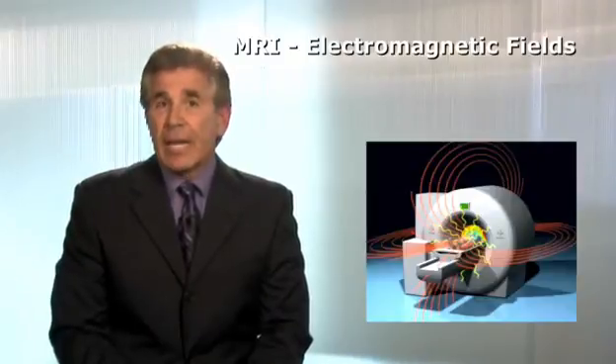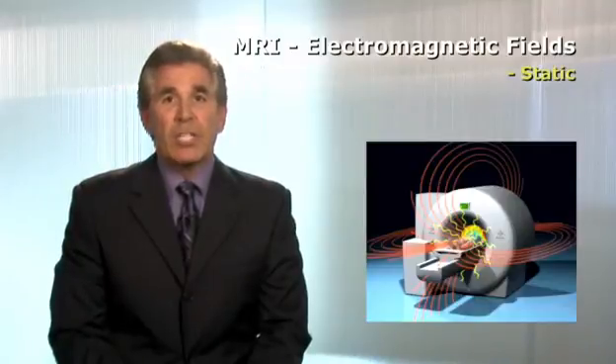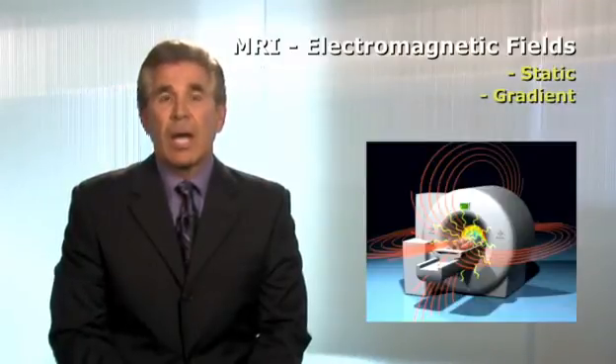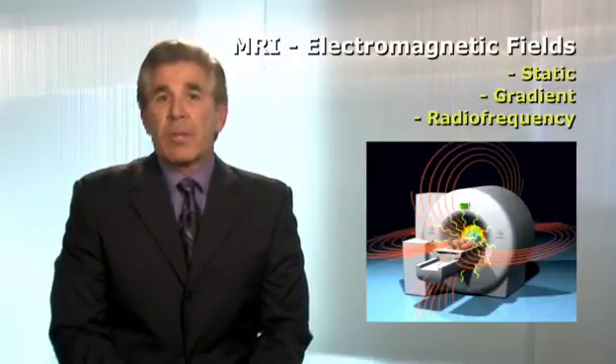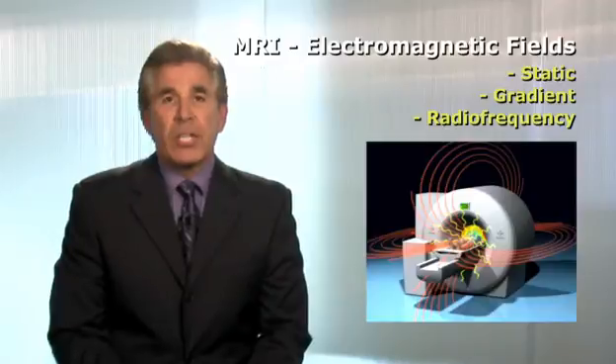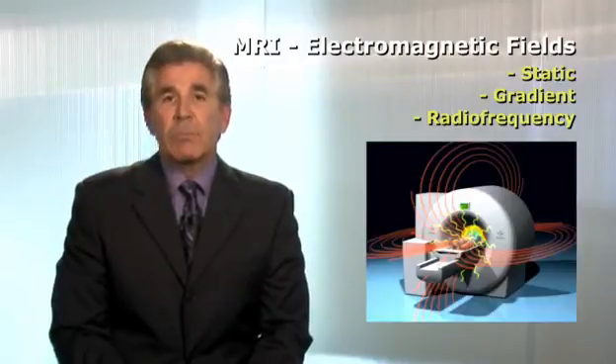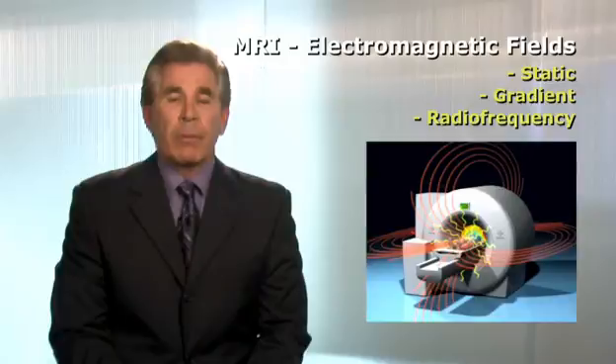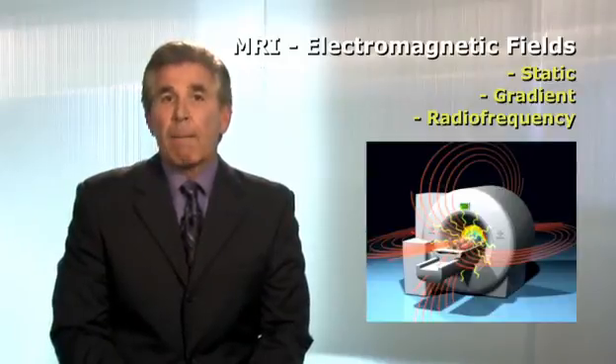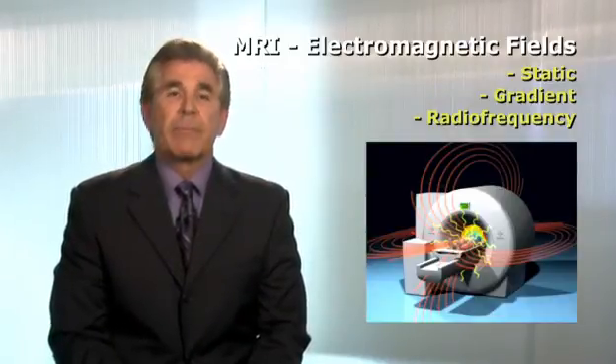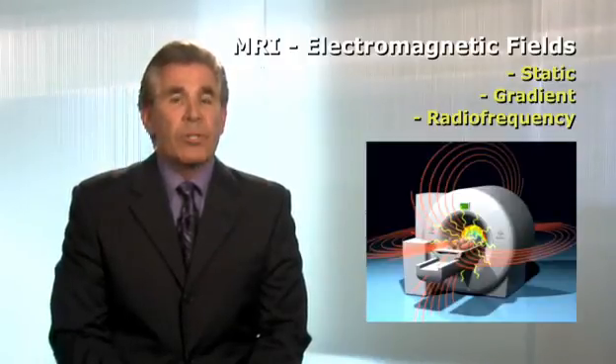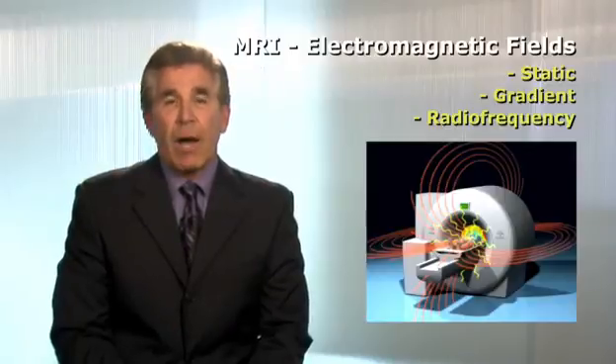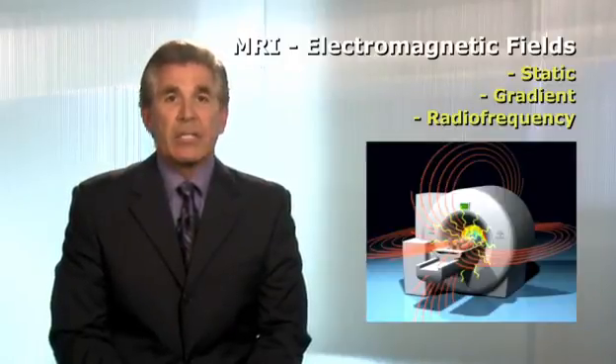If these electromagnetic fields are used at excessive levels, they can interact with the patient's body and potentially produce undesirable physiological changes. However, for the majority of the hundreds of millions of patients that have undergone MRI exams, only a small percentage have experienced problems, which have included minor to serious injuries and several fatalities. In general, these incidents occur due to improper uses of MRI technology and or from not following appropriate safety guidelines and procedures.